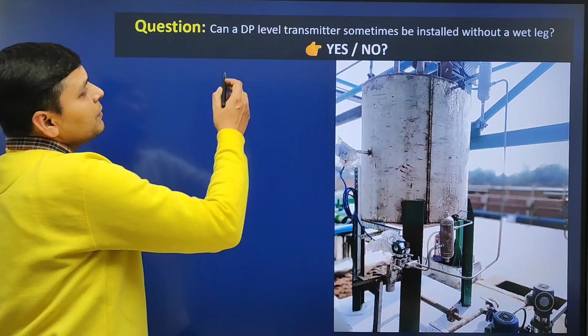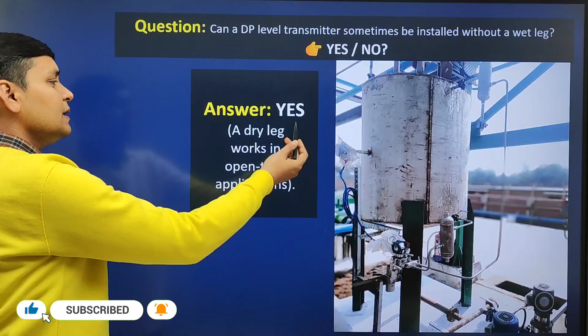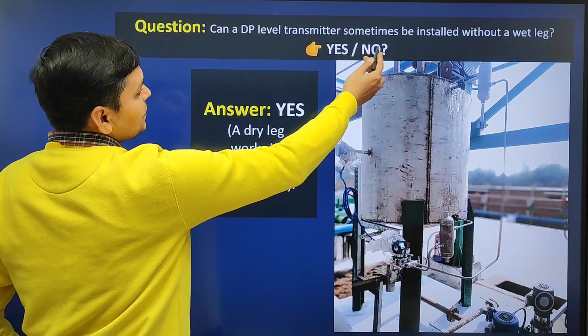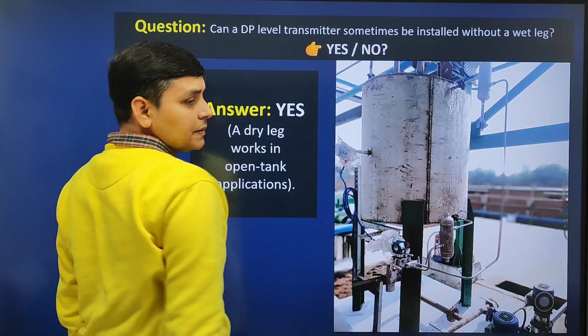The next question is, can a DP level transmitter sometimes be installed without a wet leg? Yes or no? The answer is yes. A dry leg works in open tank applications. If we are using DP level transmitter for open tank applications, then we can install it without a wet leg.